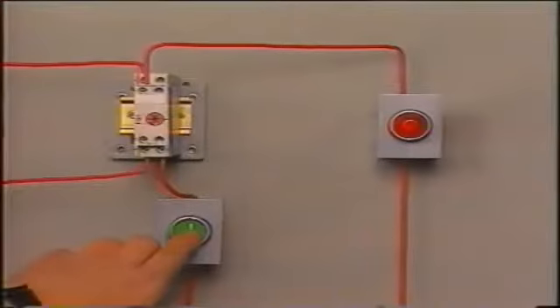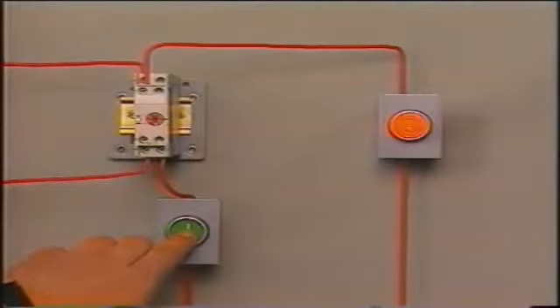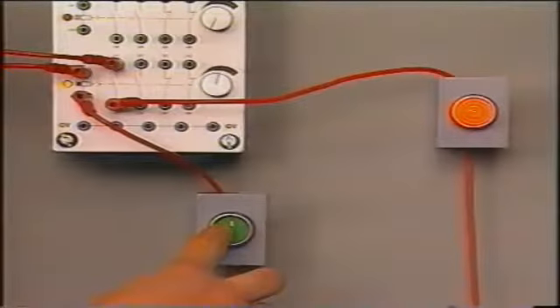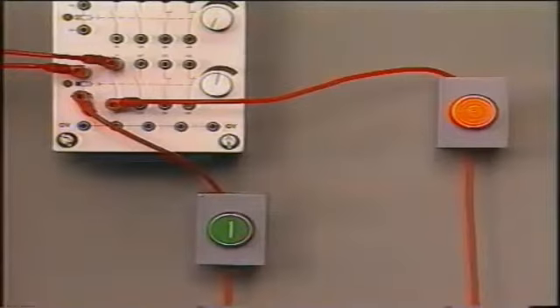This pickup delay relay does not switch until the control signal has been present for a preset time. This time is adjustable. The elevator door is an example. When it is closed and the door contact gives a signal, there is a pause before the elevator is set in motion. The dropout delay relay works the other way round. When the control voltage in the coil is interrupted, there is a pause before the relay drops out. Here's one in a car. The door contact interrupts the control circuit, and the light goes out after a short pause.